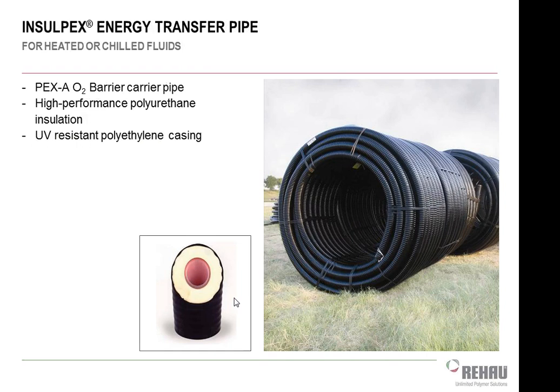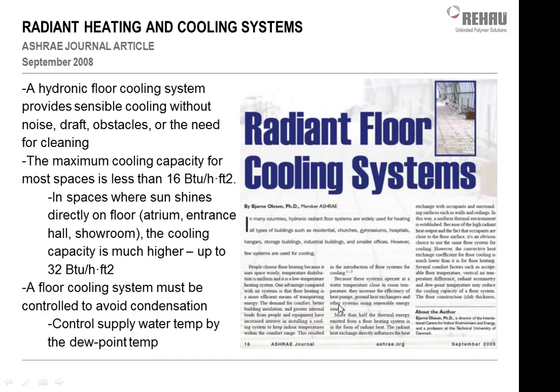Because we're running out of time, we'll just flash through those and mention the last couple things. We do also use PEX for other applications. We use it for heat transfer piping. So if I have to run a line between an outdoor chiller and an indoor building, I might get pre-insulated PEX and bury it underground. It's fairly easy to run. It comes in large rolls. So we do that quite frequently around here.